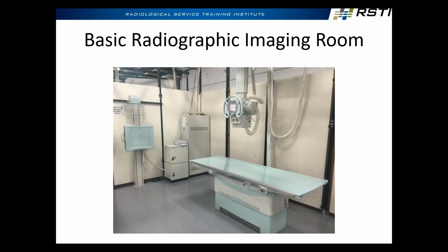Here we have a basic rad room. In this little basic rad room, we have our elevating table with a table bucky. We have a wall stand with a wall bucky. The bucky assembly is where our image receptor would go. This one was probably initially designed to be used with analog image receptors. It's that same style of tray, but it can be used with film, with computed radiography, with digital radiography. We have DR panels now that are the same specs, the same geometry as your film cassettes, so they can go right in there as well.